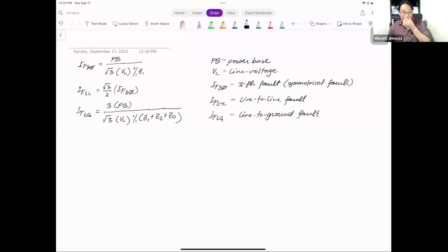Likewise, we will also use the formula to convert per-unit values from old base to new base: Z new in per-unit equals Z old times (power base new over power base old) times (voltage old over voltage new) squared.